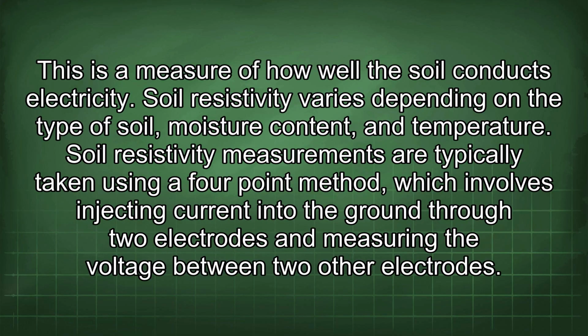This is a measure of how well the soil conducts electricity. Soil resistivity varies depending on the type of soil, moisture content, and temperature. Soil resistivity measurements are typically taken using a 4-point method, which involves injecting current into the ground through 2 electrodes and measuring the voltage between 2 other electrodes.